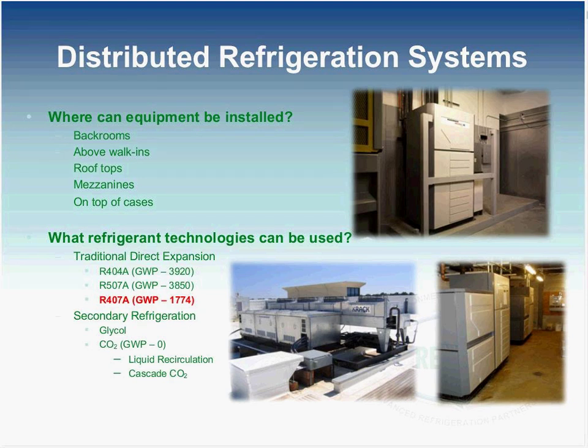And then as far as the refrigerant technology that you can use with it, we typically see 404A systems that have been out there with the changeover from HCFCs to HFCs. But with the lower GWP refrigerants such as R-407A, we're seeing a lot more customers look at that refrigerant as a benefit on the global warming potential that it has in comparison to the more traditionally used HFCs. And you can also use distributed type systems with glycol and CO2 as a liquid recirculation or cascade. So there's different options either available today or forms of those that customers have done some unique designs with to again displace the use of HFC refrigerants in their store and further reduce the amount of HFC refrigerants that they're using.